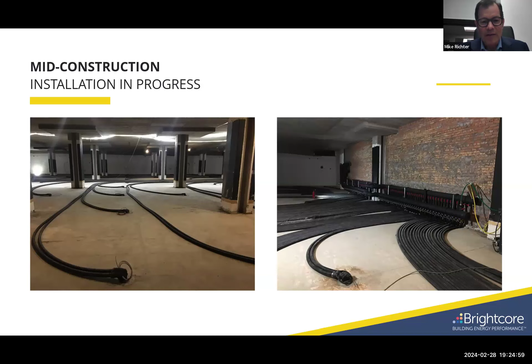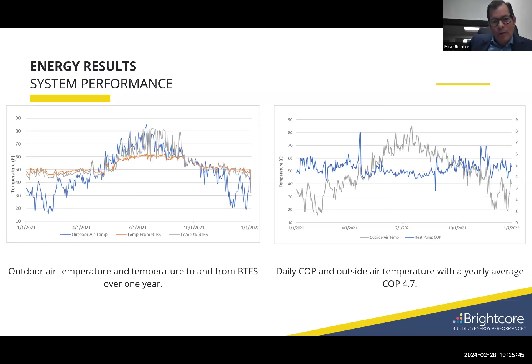I'll rip through this since we're a bit thin on time, and John can correct me in the Q&A where he's on the panel. The air temperature, shown in blue, goes up and varies, but the temperature from the borehole thermal storage is very consistent across time. That 55-degree ambient temperature doesn't vary with the air temperature across seasons or across the day. So it's extraordinarily important: the coefficient of performance doesn't vary much. The squiggles show how the building is being used, but you have a very robust system that can handle pretty much any load.